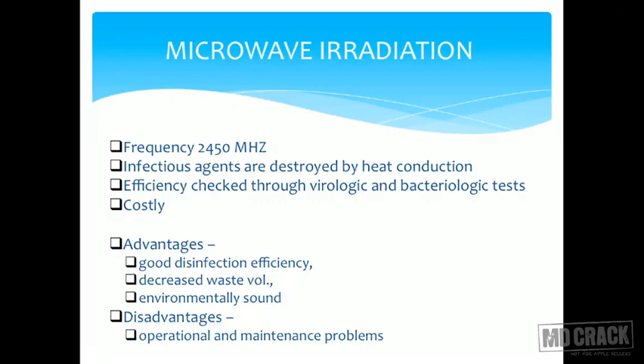Coming to the next method — microwave irradiation. As you know, we use microwaves in our households for cooking food. The frequency used for disinfection is 2450 MHz. Infectious agents are destroyed by heat conduction — they are heated and thus killed. Efficiency has to be checked through virological and bacteriological tests repeatedly, so you have to keep an eye on the efficiency of microwave irradiation. And of course, it is costly.